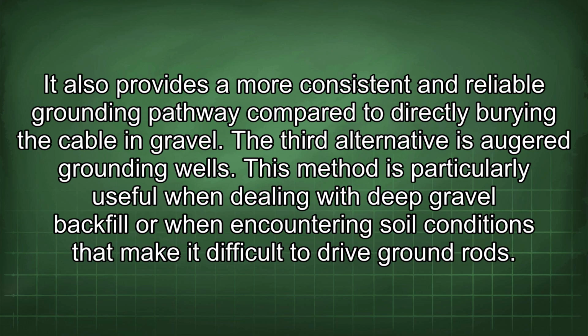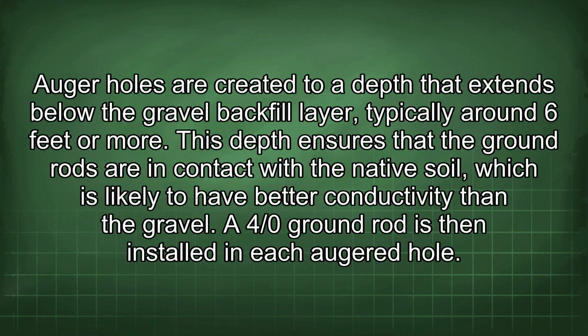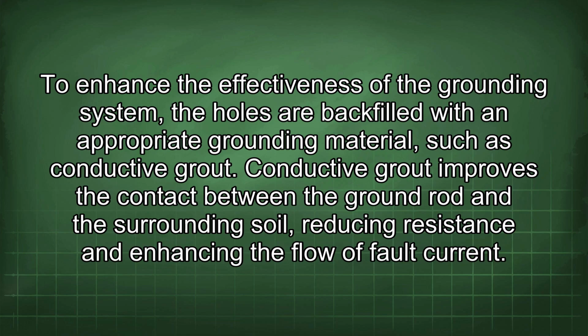The third alternative is augered grounding wells. This method is particularly useful when dealing with deep gravel backfill or when encountering soil conditions that make it difficult to drive ground rods. Auger holes are created to a depth that extends below the gravel backfill layer, typically around 6 feet or more. This depth ensures that the ground rods are in contact with the native soil, which is likely to have better conductivity than the gravel. A 4/0 ground rod is then installed in each augered hole. To enhance the effectiveness of the grounding system, the holes are backfilled with an appropriate grounding material, such as conductive grout.